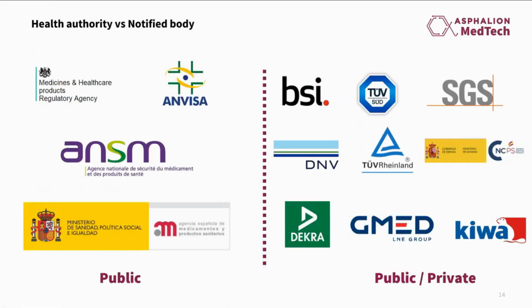So we have commented on notified bodies, but what are European notified bodies actually and how do they differ from competent authorities? Notified bodies are public or private companies that are designated by the competent authorities of the member state where they are established. And basically, these are the regulatory bodies responsible for assessing the compliance of a medical device, remember, higher than class 1 or higher than class A, with the applicable legal framework, the MDR or the IVDR as applicable. So these will be the entities that will, in the end, affix the CE mark to your device.